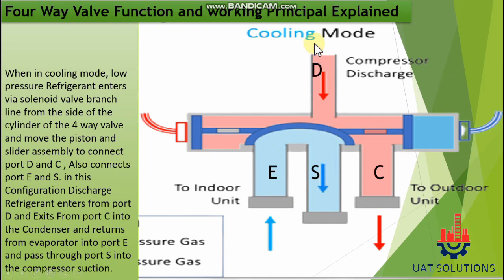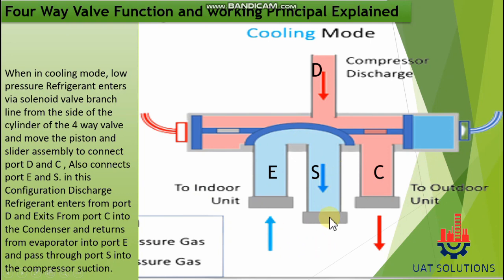In this configuration, discharge refrigerant enters from port D and exits from port C into the condenser, and returns from the evaporator into port E and passes through port S into the compressor suction.